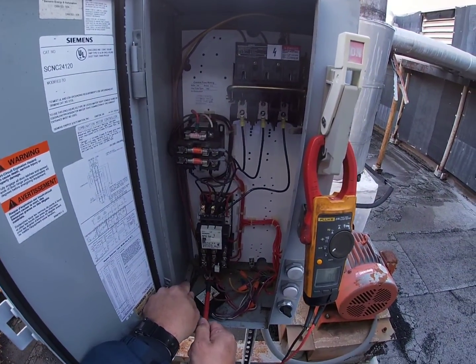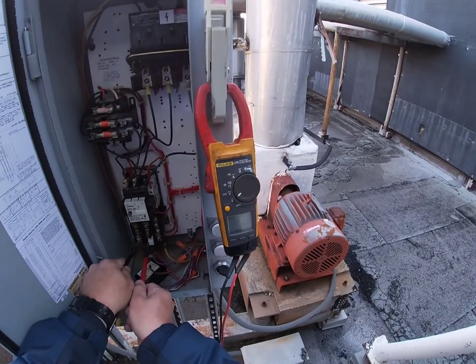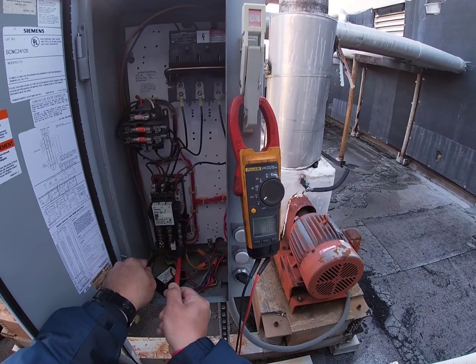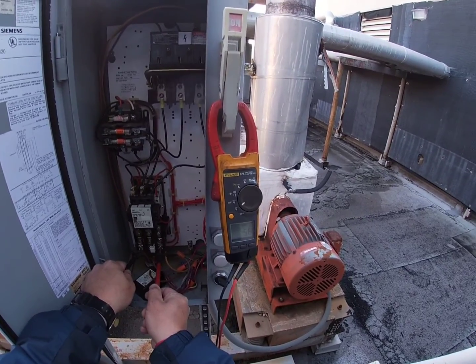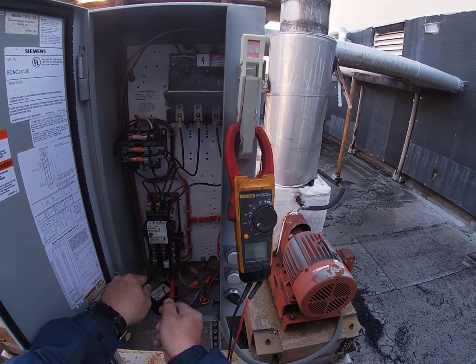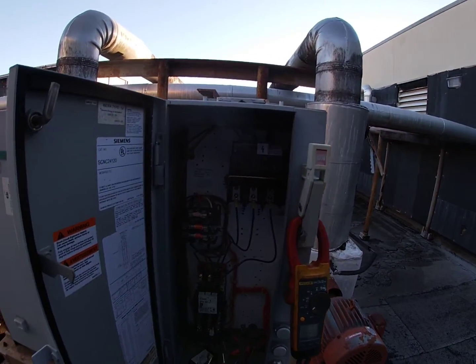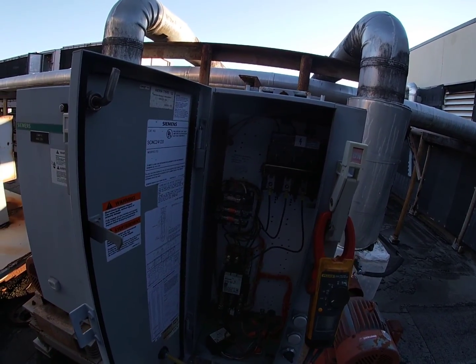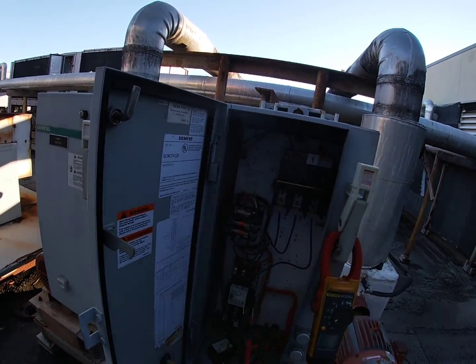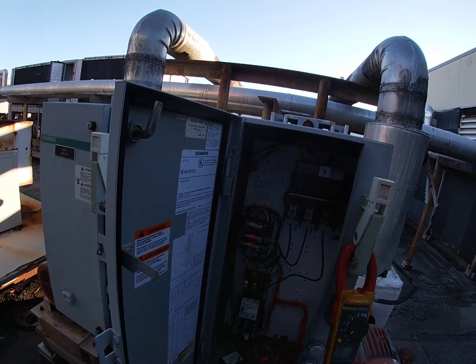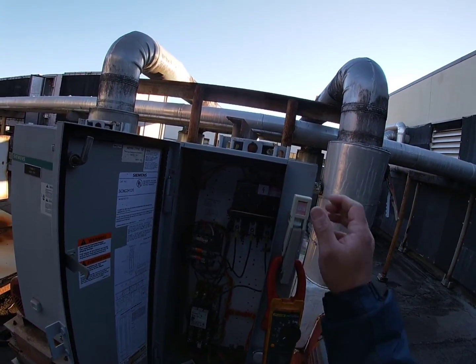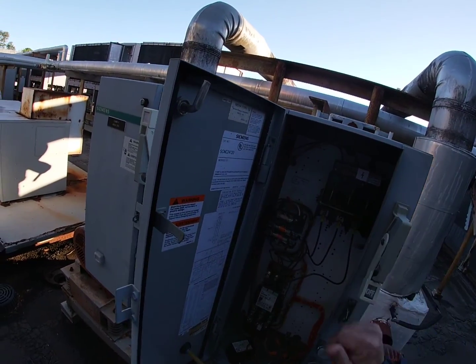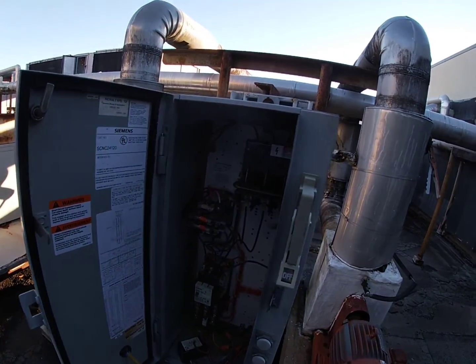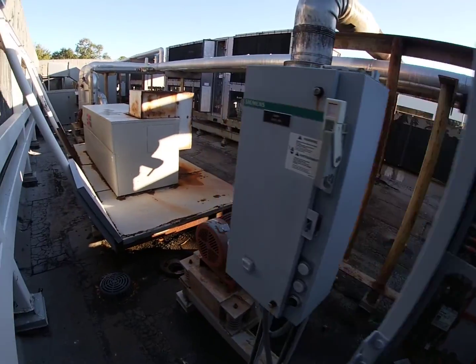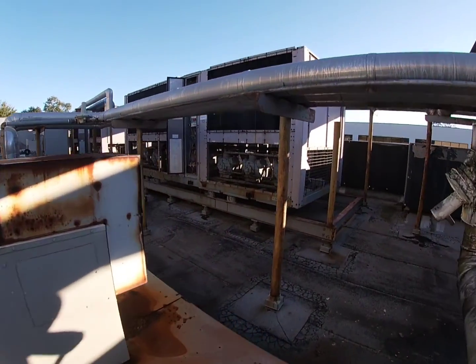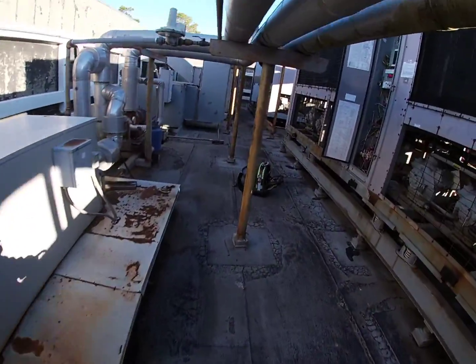But we're gonna go from here to here, and as you can see, 4 volts. Here to here, 5 volts. Here to here, we have 480. So we're losing a phase on that contactor there. So it's just a bad contactor, that's all it is. So we're gonna turn it off. We're gonna go ahead and megger the motor anyways, just to be on the safe side here. So let's go get my leads for that.